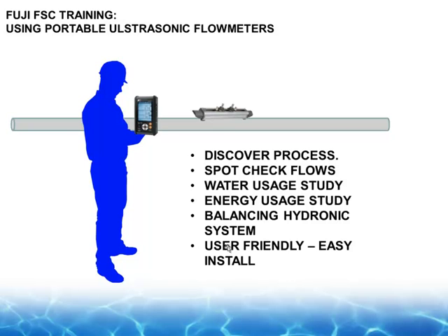The portable ultrasonic transit time flow meter is designed for ease of use. It has evolved away from the big old suitcases of days of yore, where you had to carry around your 20, 30-pound big box to monitor your liquid applications. It's about the size of a big voltmeter. It's designed for ease of use and the discovery process. So if you need to design a new chiller plant, you need to know what your current flow rates are before you make an investment in that facility. So a discovery process with a portable device, either spot checking or leaving it there for a period of time, will allow you to compile all the data you need based upon your current statistics.